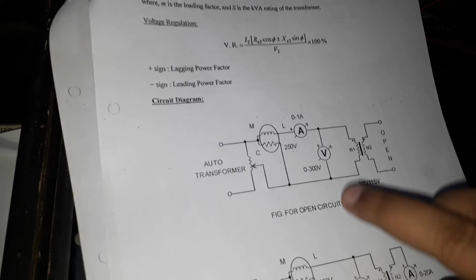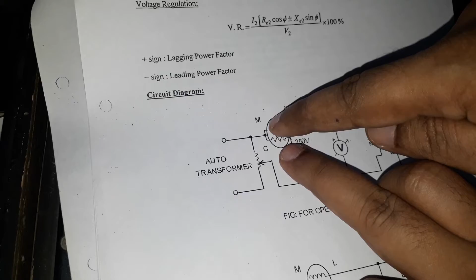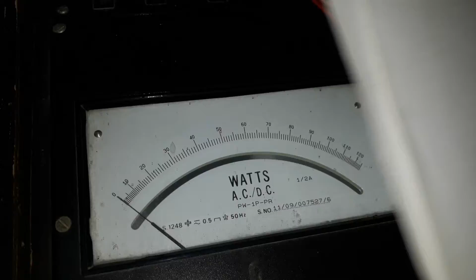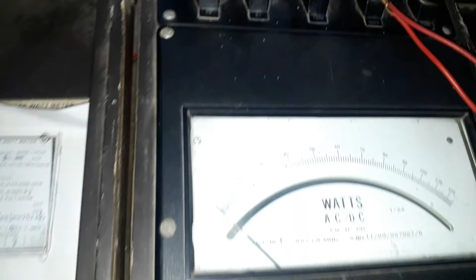If you see where the auto transformer terminals are connected, one terminal of the auto transformer is connected at the point where we have short circuited M and COM, and the other end is going to be connected to the return path of the circuit which we have brought to 250 volt. So one end of the auto transformer supply will be connected at 250 volt while the other will be connected at M and COM. So this circuit is complete. Now I am switching it on and I will show you how to take the readings.